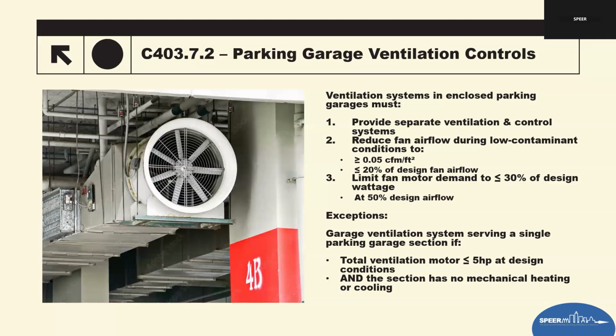This requirement drives the use of variable speed drives such as VFDs or ECM motors, which most of them are made with now anyways, or a high efficiency fan system. So this protects against inefficient throttle control fan systems that waste a lot of energy. And there is an exception. It's designed for very small garages. So the ventilation system motor must be 5 horsepower or less. That's what's going to determine it to be a very small garage. And the garage parking section must have no mechanical cooling or heating. So if both are true, the advanced turn down and power requirements do not apply.